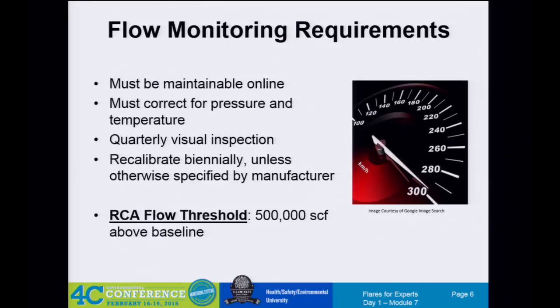Test the flow meters? No, they're not a CEMS. So there are examples where you have to RATA test flow meters. You can do a performance test on a flow meter, the same way you do a test if you have a CEMS RATA for an FCC, where you might have an annubar measuring the flow. You can test that against a standard method, reference method 1 through 4, whatever, and you'll get a number that tells you how accurate that flow sensor is. But nobody's going to take the time to do that in a flare unless they're crazy. And it's not required by the regulation. Yeah, no, they didn't put the requirement in for any RATA testing.